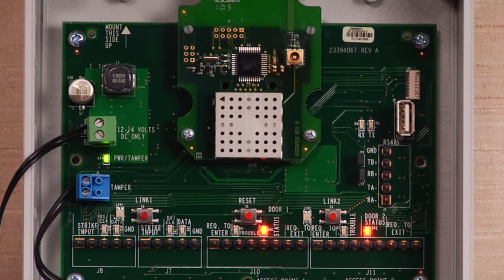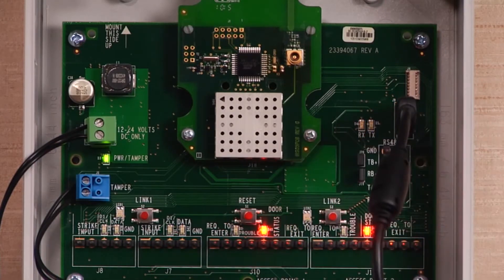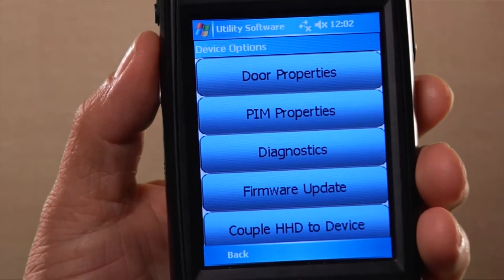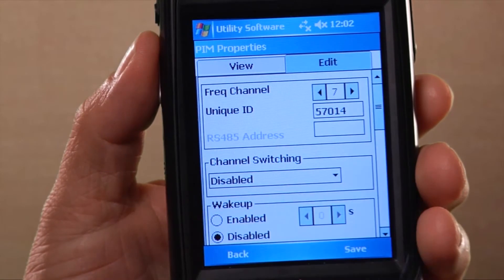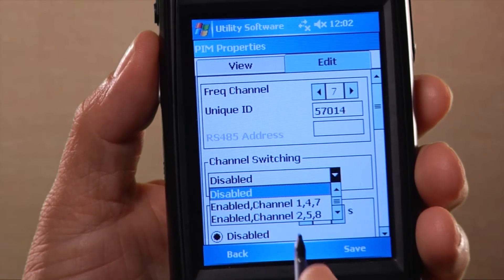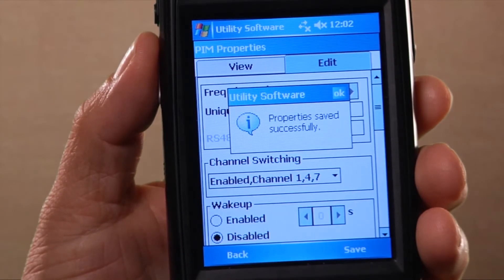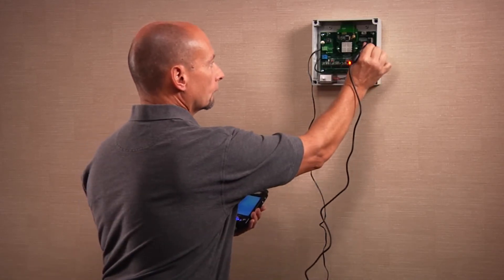To turn DCS on, connect the HHD to the PIM 400 TD2 and log in to the Schlage utility software. When the PIM appears in the device list, tap Device Options, then tap PIM Properties. Tap the Edit tab and locate the Channel Switching option. Select any DCS channel group. Tap Save. At the confirmation screen, tap OK. Exit the utility software and disconnect the HHD from the PIM.